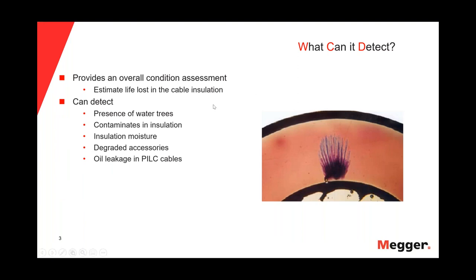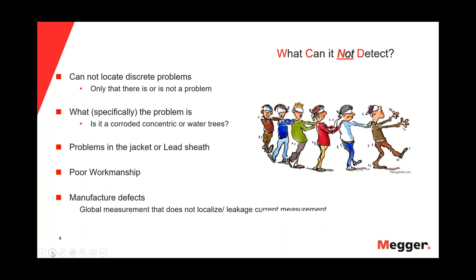What can Tan Delta detect? It provides an overall condition assessment, estimates life lost in the cable insulation, and can detect the presence of water trees, contaminants in insulation, insulation moisture, degraded accessories, and oil leakage in PILC cables. What it cannot detect: it cannot locate discrete problems — only that there is or is not a problem. It is a global assessment that does not localize. It cannot determine specifically what the problem is — whether a corroded concentric, a water tree, or a dirty termination. It also cannot detect problems in the jacket or lead sheath, or isolate poor workmanship or manufactured defects. Essentially, this is fundamentally a leakage current measurement.